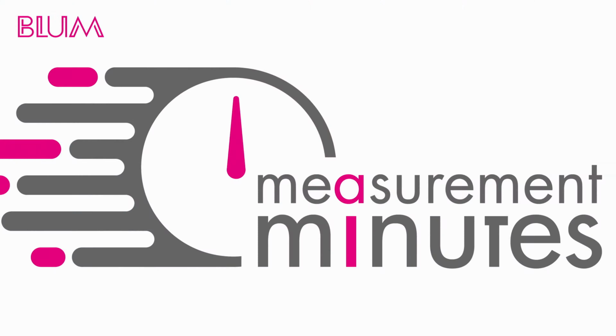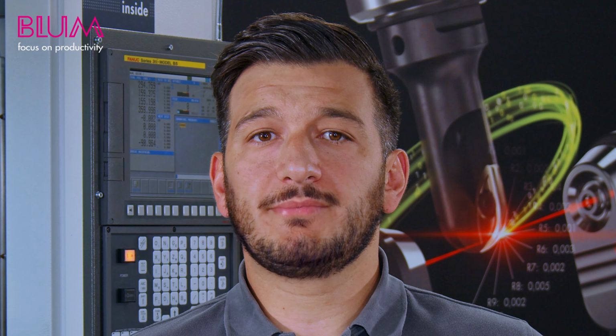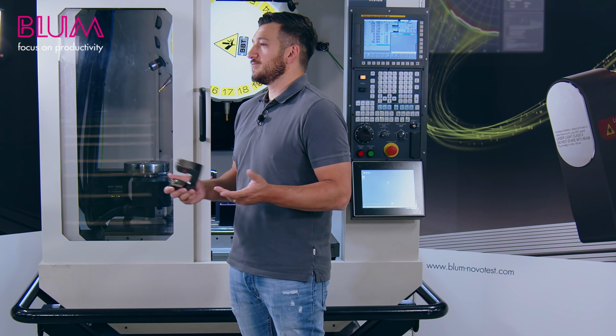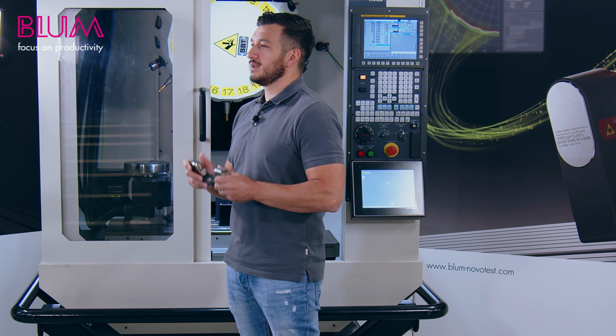Perhaps you're wondering when I need to calibrate. Quite simply, for example, if you have moved your system or dismantled it and now want to measure again. Or if you simply want to measure accurately, I would always recommend calibrating your system when the machine is at operating temperature, then measuring your tools. In other words, during the setup process - these would be reasons and times when you should calibrate.